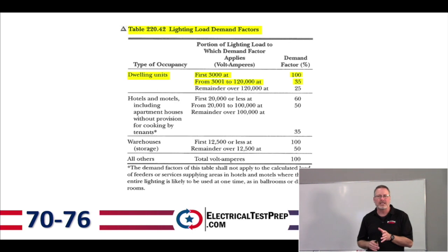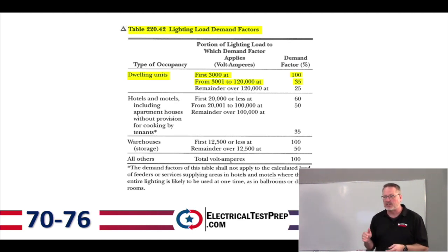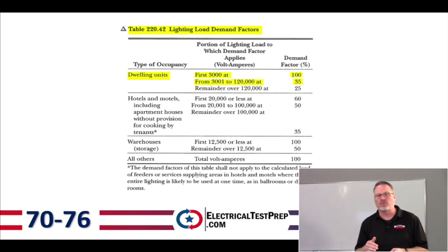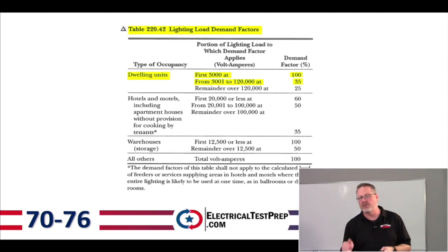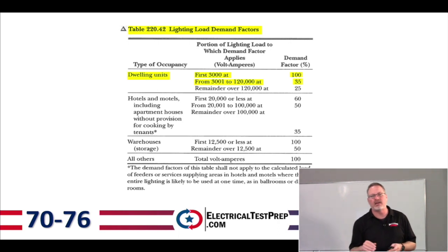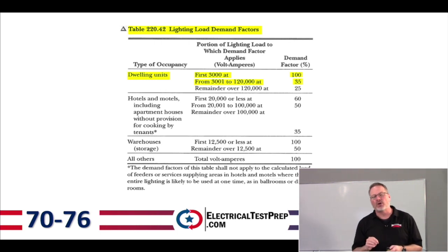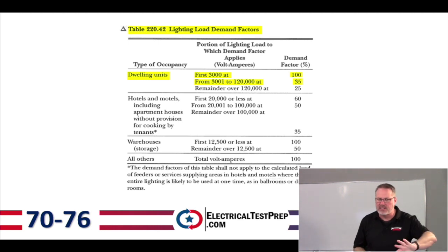For a dwelling unit: the first 3,000 volt-amps is calculated at 100%, and from 3,001 to 120,000 volt-amps, we calculate at 35%. We'll work through problems showing how to apply this. Just know this is the table where we derate the load.